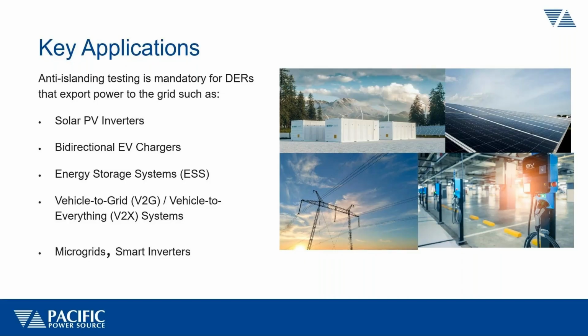So another category here, of course, are battery backup systems or energy storage systems that are used to supplement grid power. They are also syncing to the grid and pushing energy back when there's a need to do so because of demand. But if the grid has a functional failure in a section, you don't want that battery system to keep energizing that section of the grid when there is a line crew going out to repair it. So those are all categories of DERs that have to meet these similar standards in order to be fully compliant.